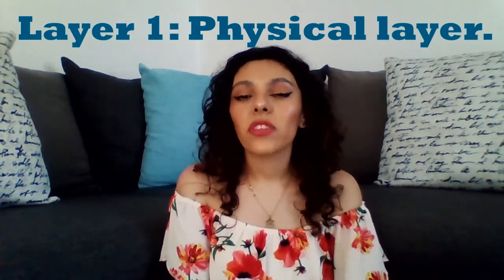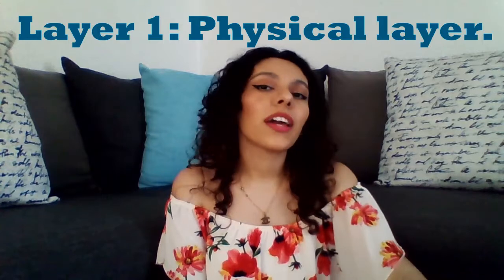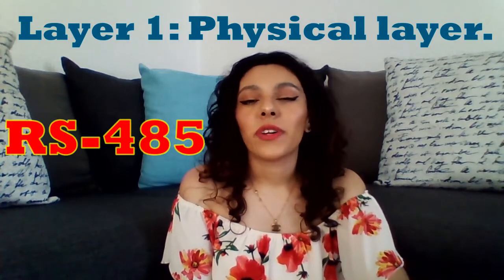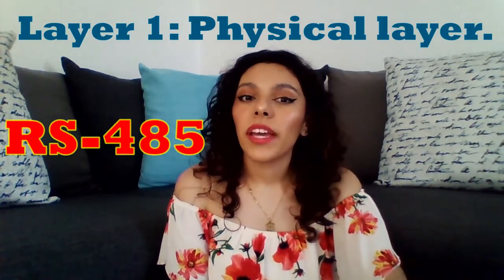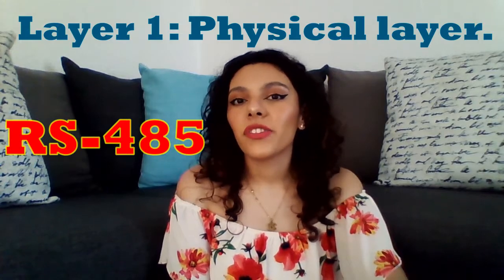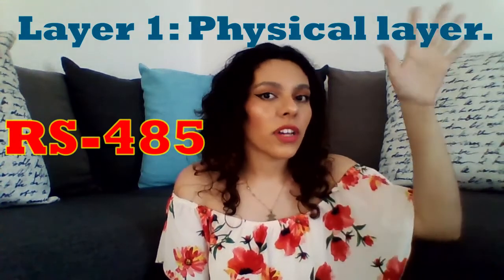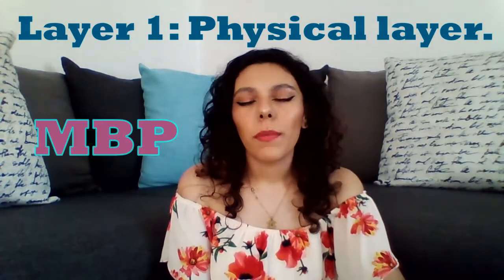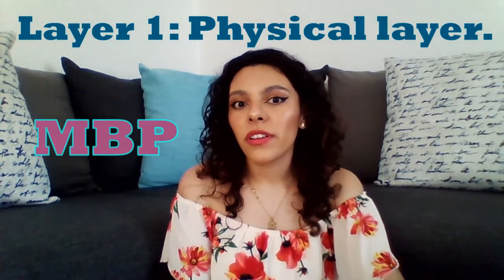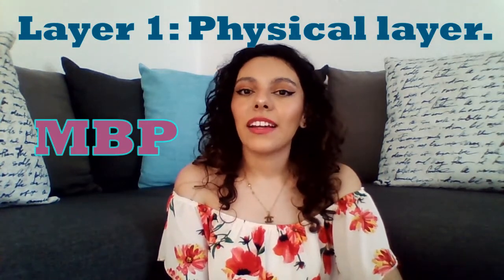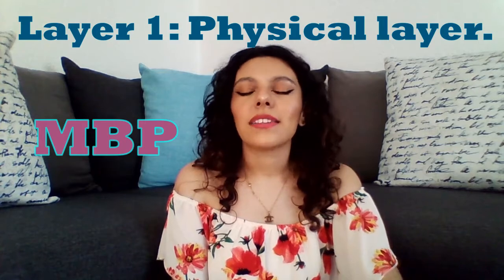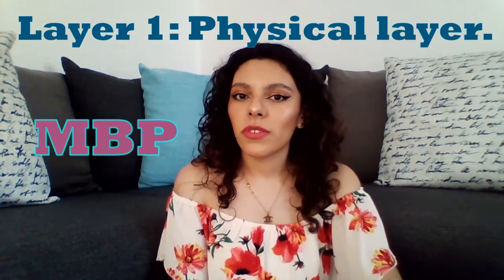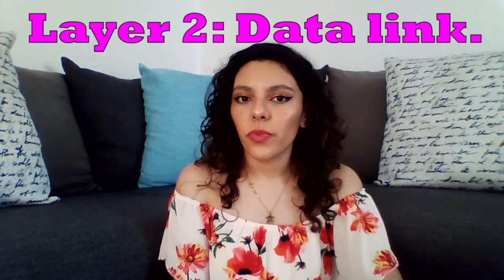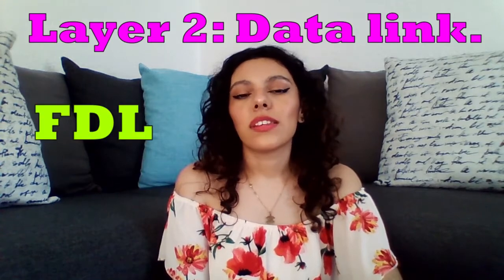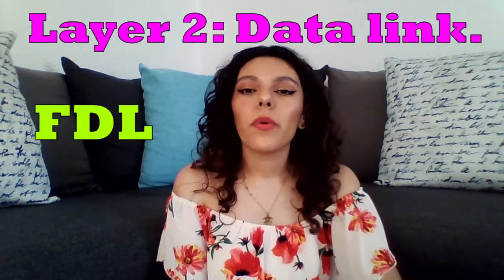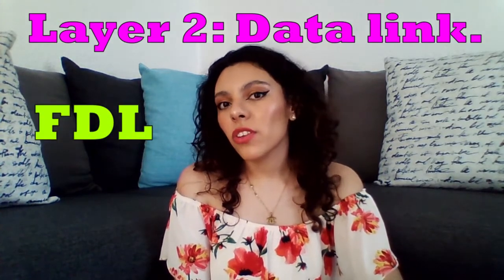PROFIBUS can have 3 types of physical communication media: the RS485, which I explained more fully in my communication video that I will also leave you here; fiber optic transmission; and Manchester coding, bus powered or MBP, which is an enhanced safety system that is available in potentially explosive environments.